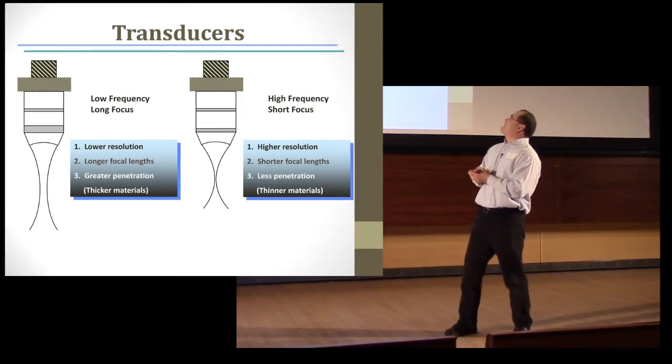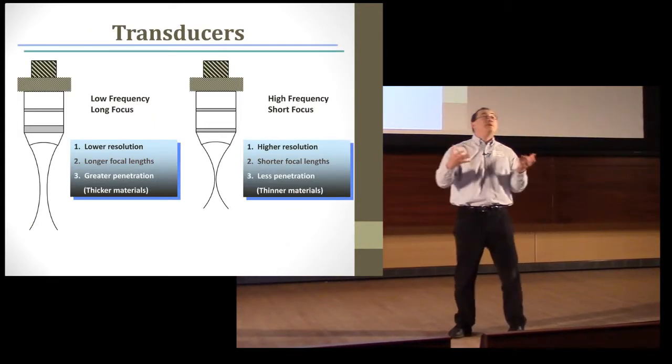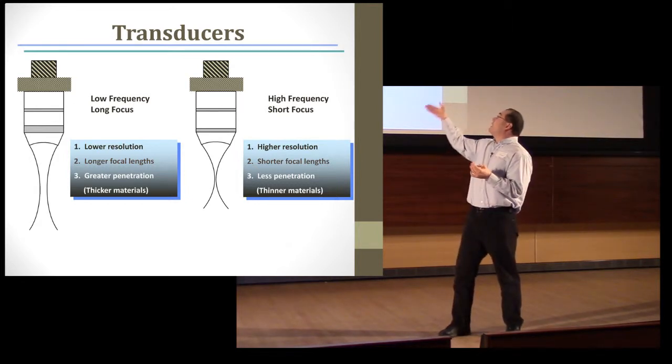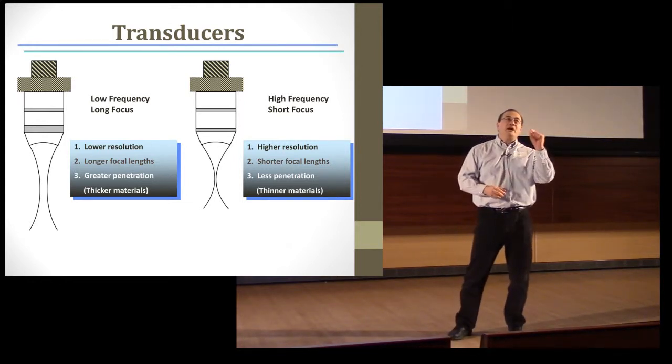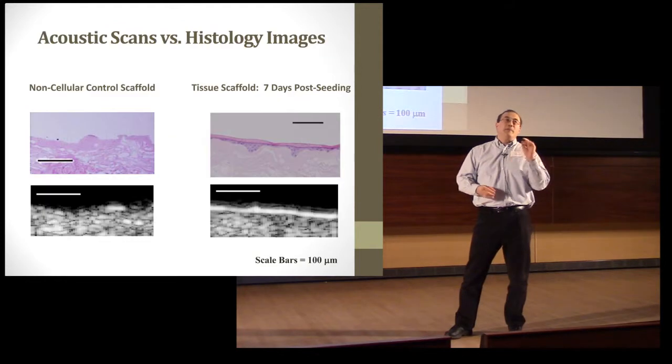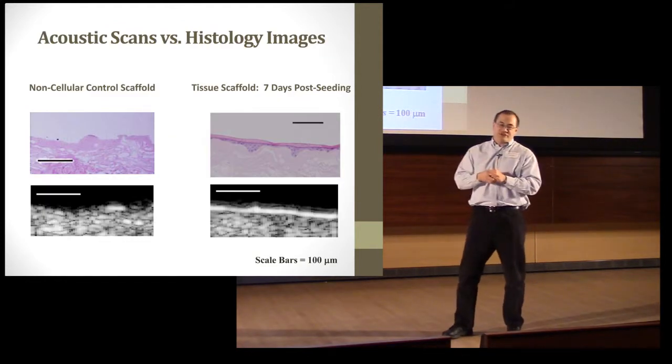Now the difference between transducers: a conventional transducer used in OB labs uses low frequency and longer focal lengths, therefore thicker materials. Ours, in contrast, is the opposite, very thin. We're not able to have very good penetration, but we can very easily image cells and tissues.